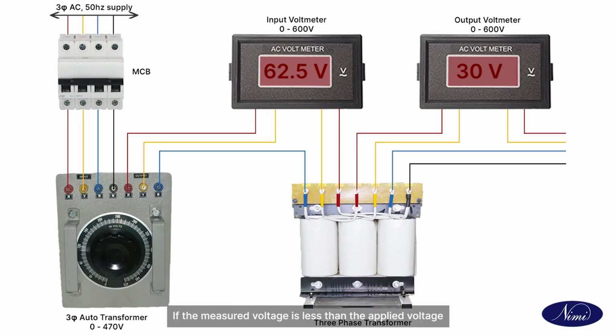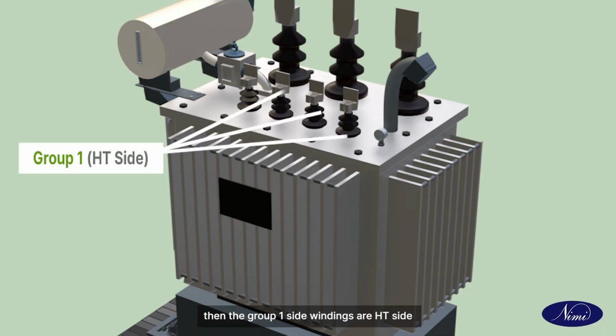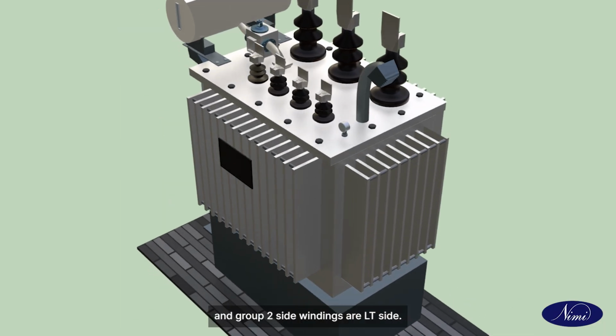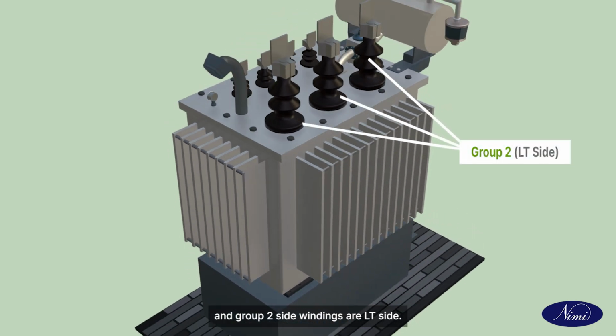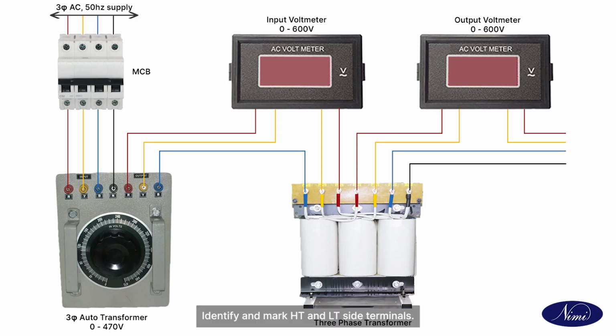If the measured voltage is less than applied voltage, then the group 1 side windings are HT side and group 2 side windings are LT side. Identify and mark HT and LT side terminals.